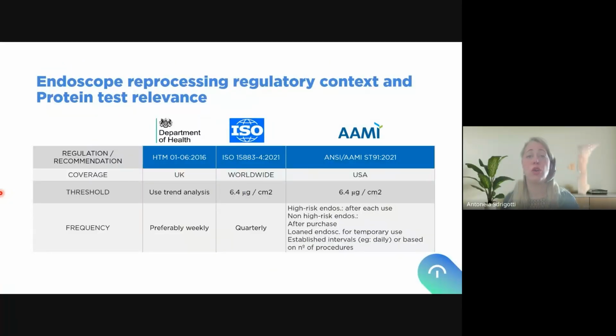So for endoscope reprocessing, we also need to review what we are going to do to verify that we actually don't have organic residues inside our channels. And this is also why, for example, the UK has long had recommendations about protein tests, related to prion outbreaks, okay? In the UK, the first prion investigations and scientific detection of these diseases took place, and this is why they adopted protein tests a long time ago for the correct verification of medical device reprocessing. But ISO and AAMI have also recently updated to recommend protein tests for internal channels, specifically for endoscopes or cannulated devices, as you can see here in these examples.